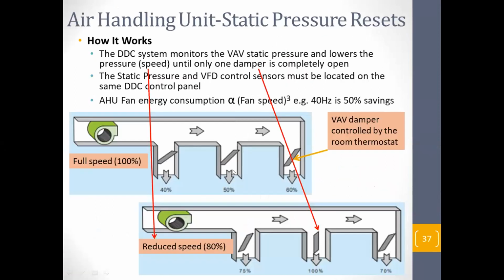Okay. One more item about the air handling units. I think in certain facilities, the VAVs can be monitored from the BMS. In certain facilities, you can't monitor VAVs from the BMS. If that is the case, make use of the duct pressure sensor and then control your VFD. When the duct pressure sensor builds up, that means the VAV doesn't need that much air, so you can reduce the speed of your VFD.